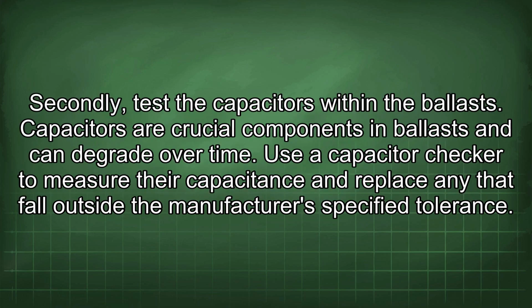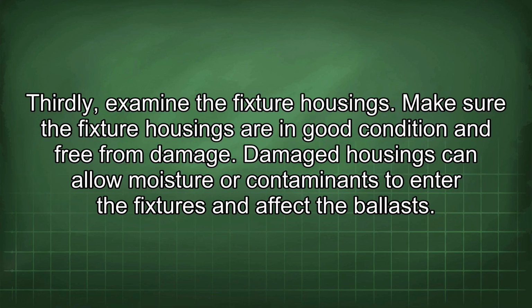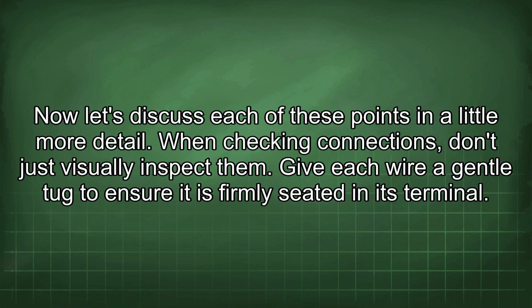Secondly, test the capacitors within the ballasts. Capacitors are crucial components in ballasts and can degrade over time. Use a capacitor checker to measure their capacitance and replace any that fall outside the manufacturer's specified tolerance. Thirdly, examine the fixture housings. Make sure the fixture housings are in good condition and free from damage. Damaged housings can allow moisture or contaminants to enter the fixtures and affect the ballasts. Now let's discuss each of these points in a little more detail.